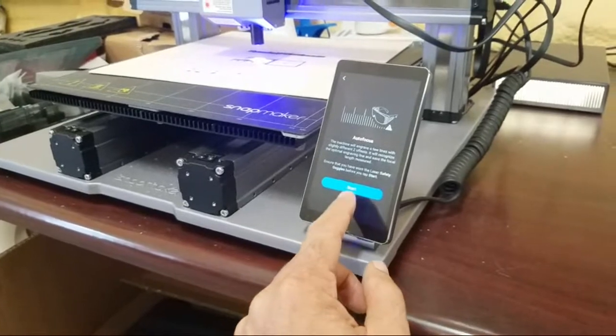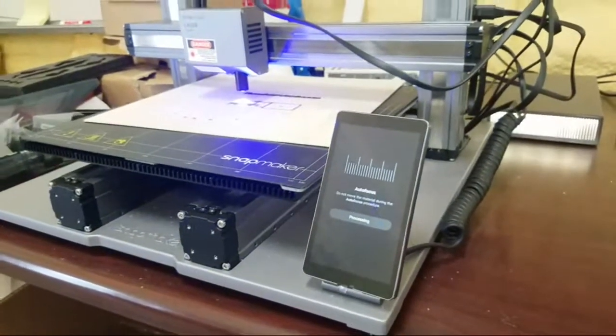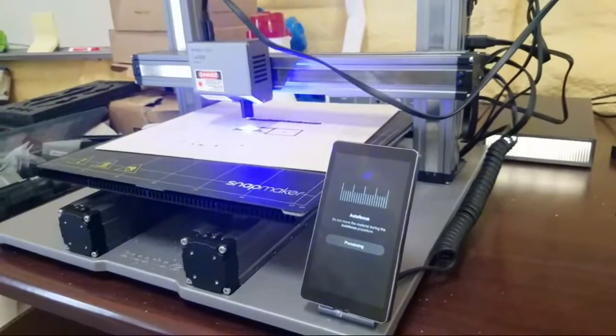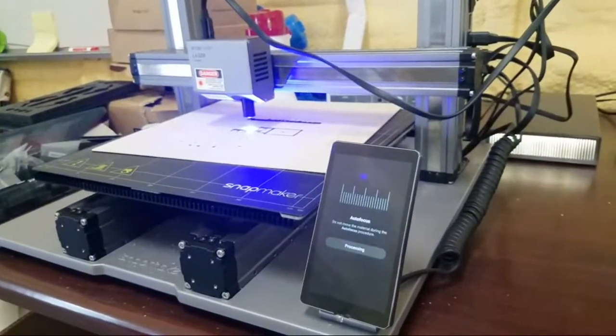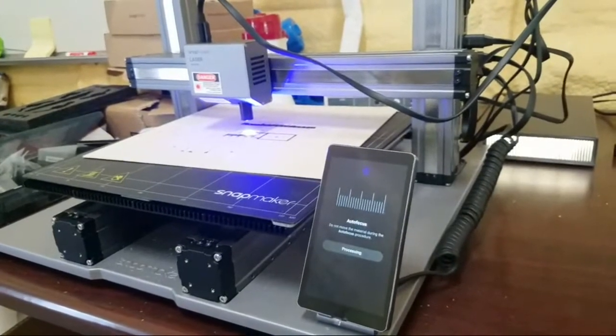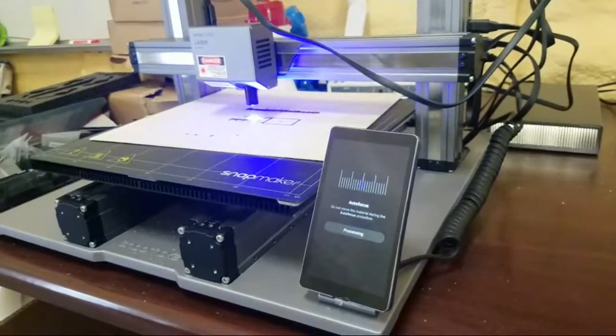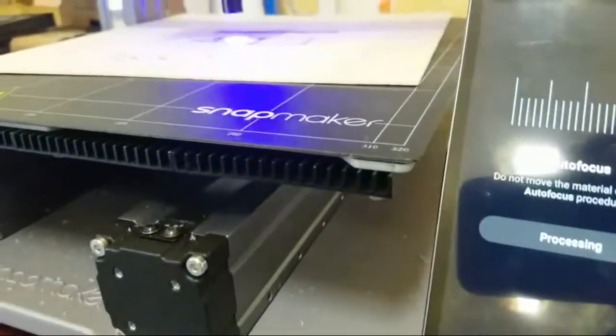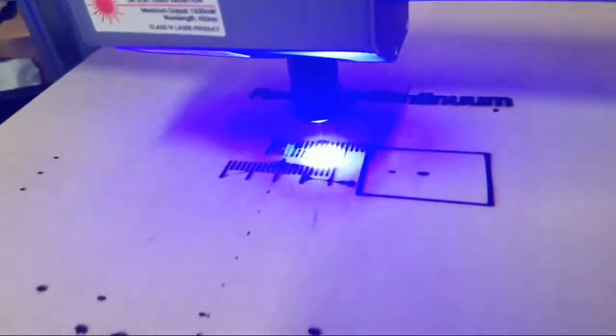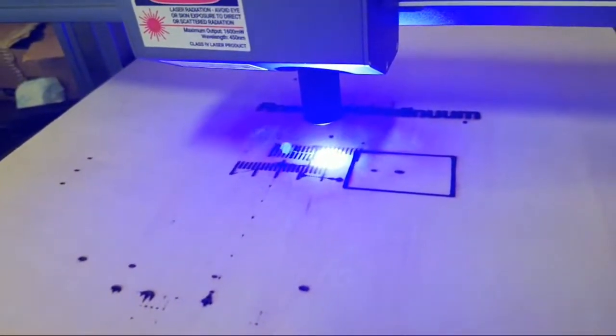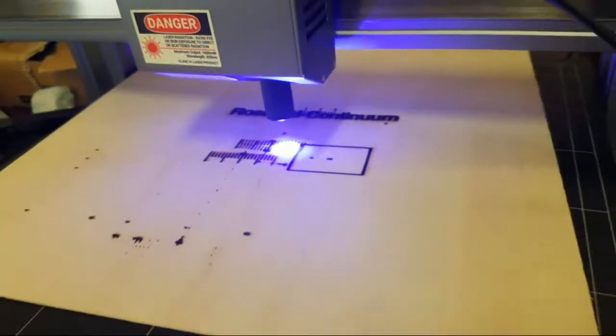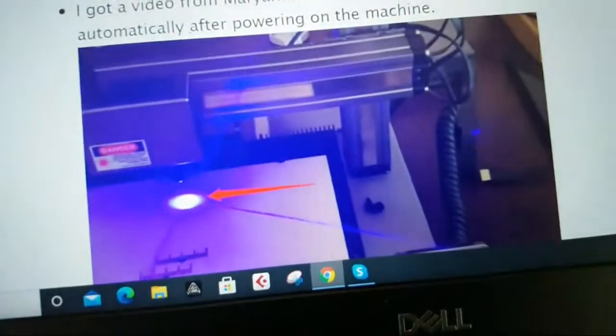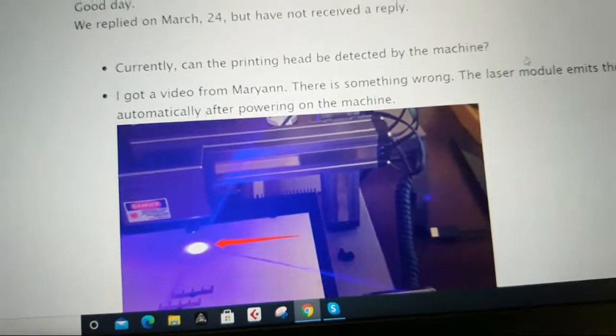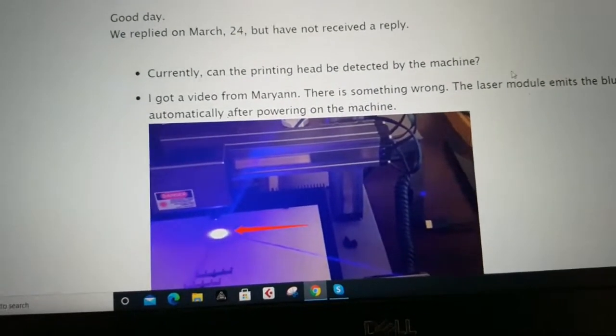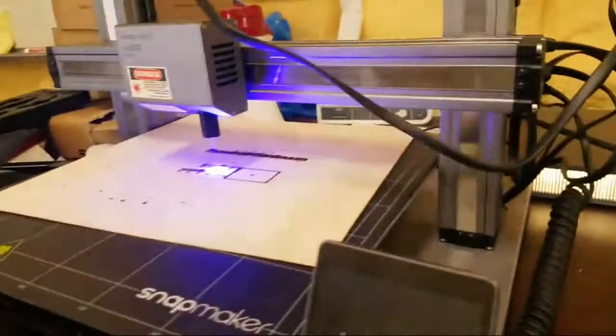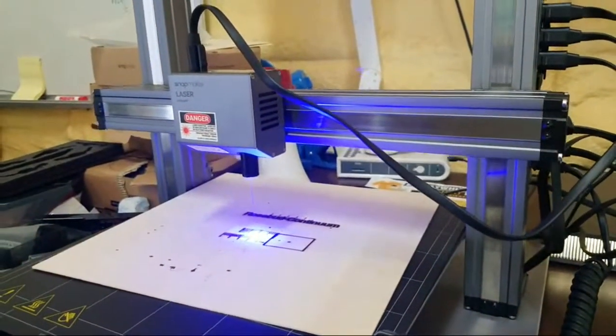So it's going to do the autofocus and it draws these lines. So we've gone through this process before, and it does the autofocus, and we've been able to carve something, but as it says here, the module is automatically emitting the blue light after powering on the machine, and that is something wrong. So that's a problem.